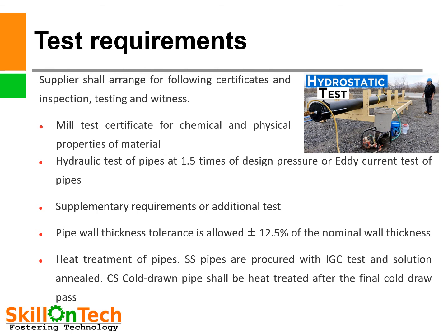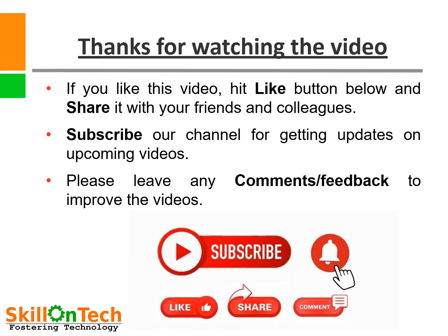Heat treatment of pipes. SS pipes are procured with IGC test — inter-granular corrosion test — and solution annealed. CS cold drawn pipe shall be heat treated after the final cold draw pass. That is all for this video.